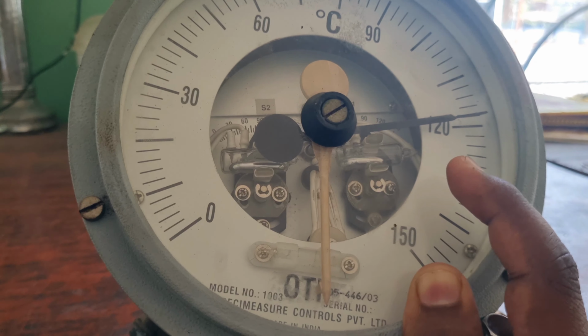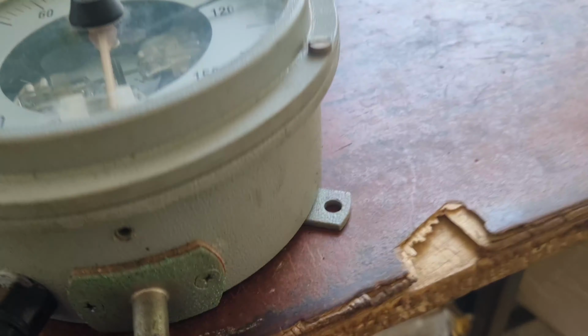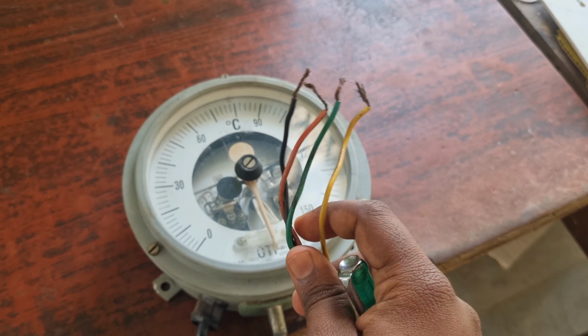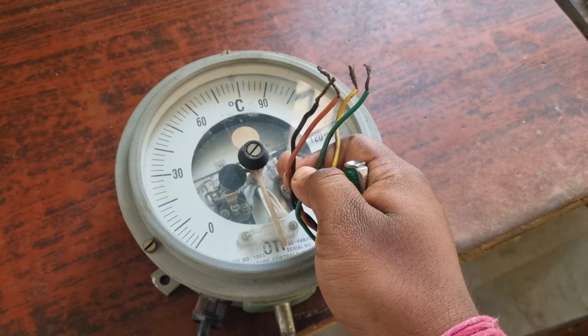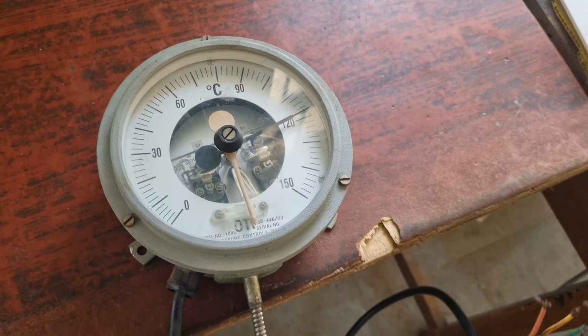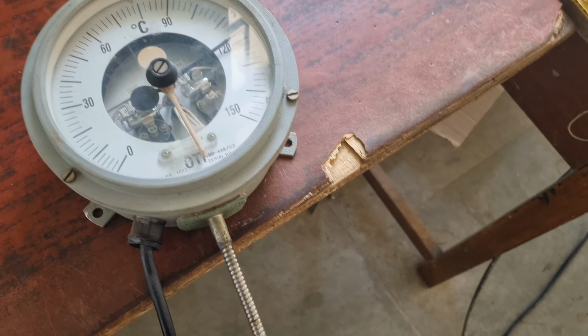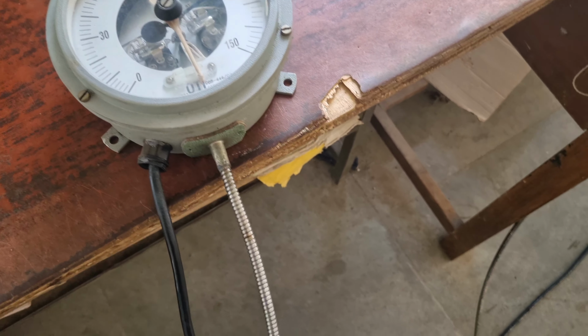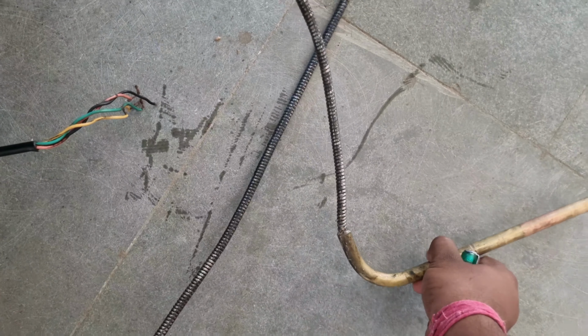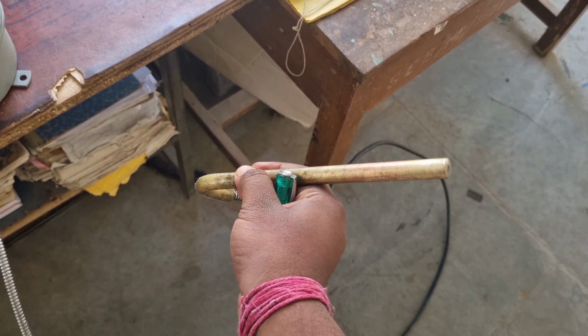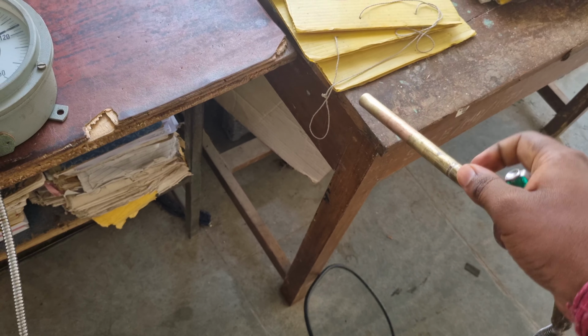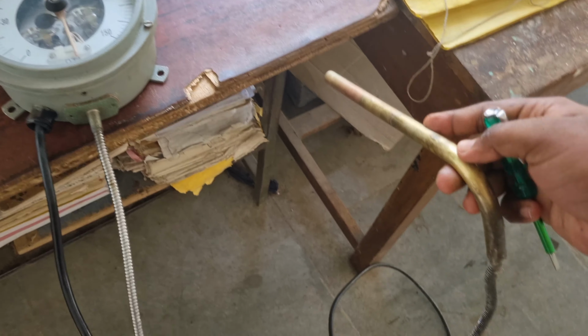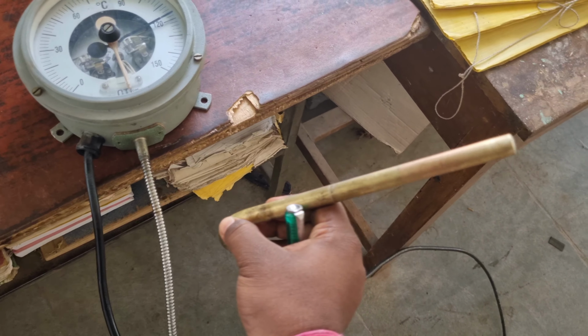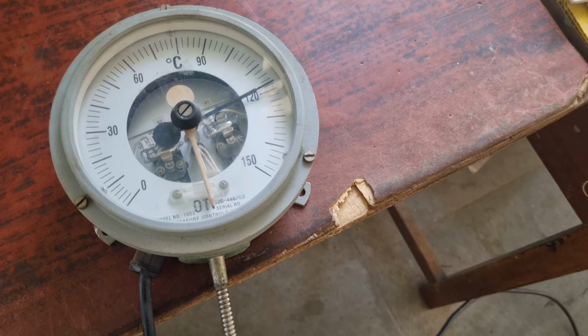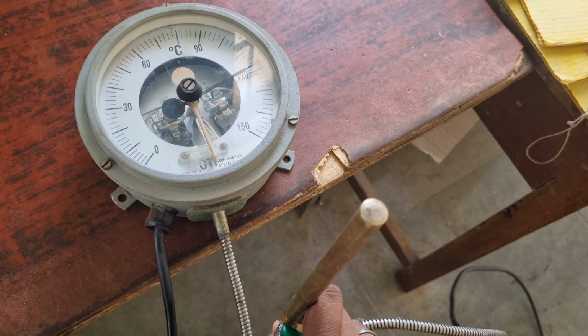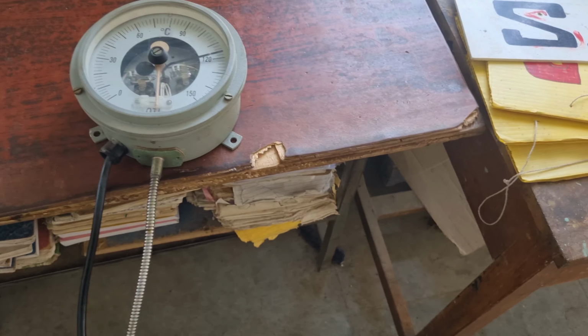In the connection, you can see at the output cable we have only 4 connections. 2 of them are for this, 2 of them are for this, and the temperature measurement actually runs through this going towards the temperature probe that is inside the transformer, which is put inside the oil chamber. This is the metal conduit, and this is the temperature probe, and that's how the oil temperature is being measured. And if I can show you...